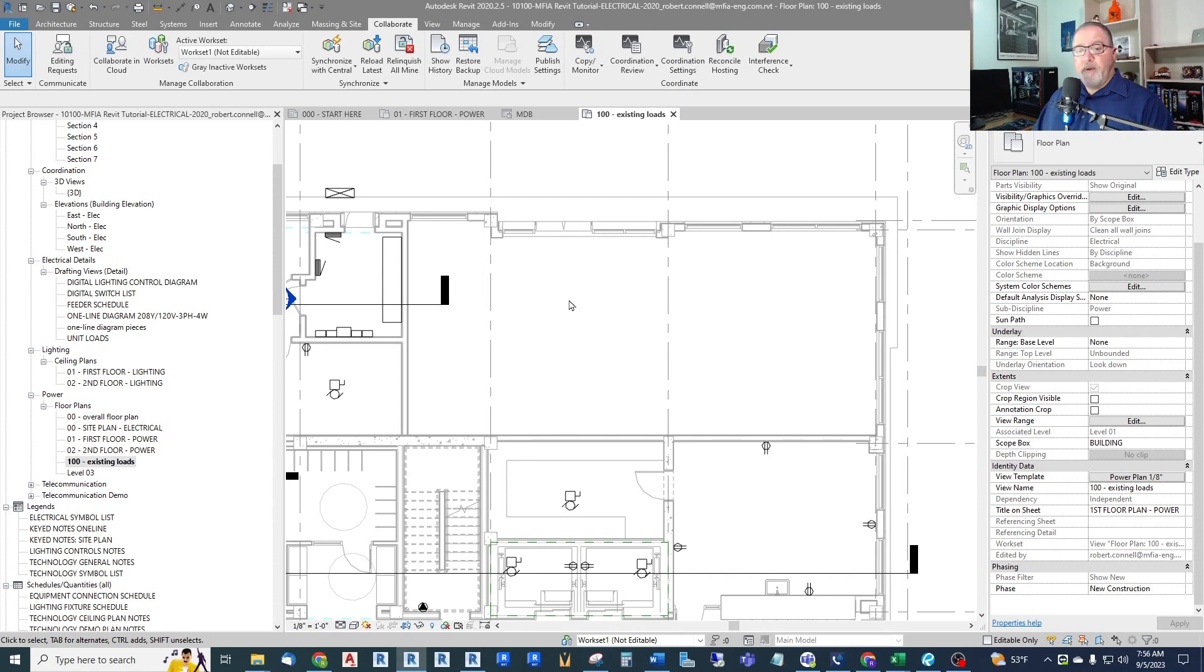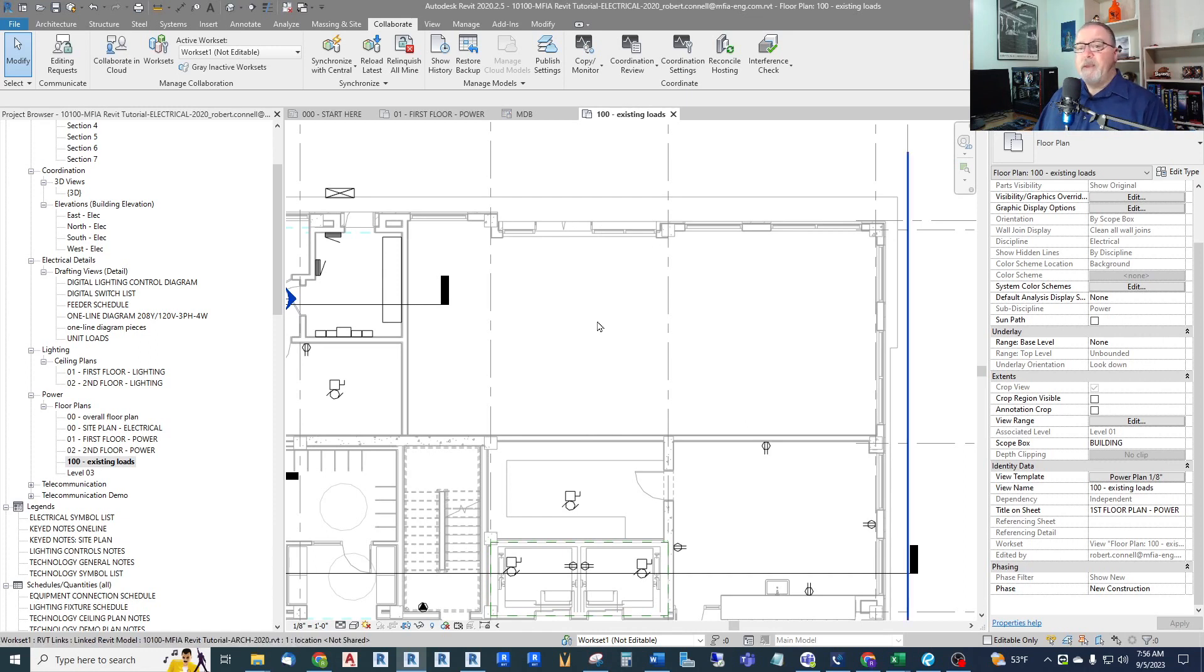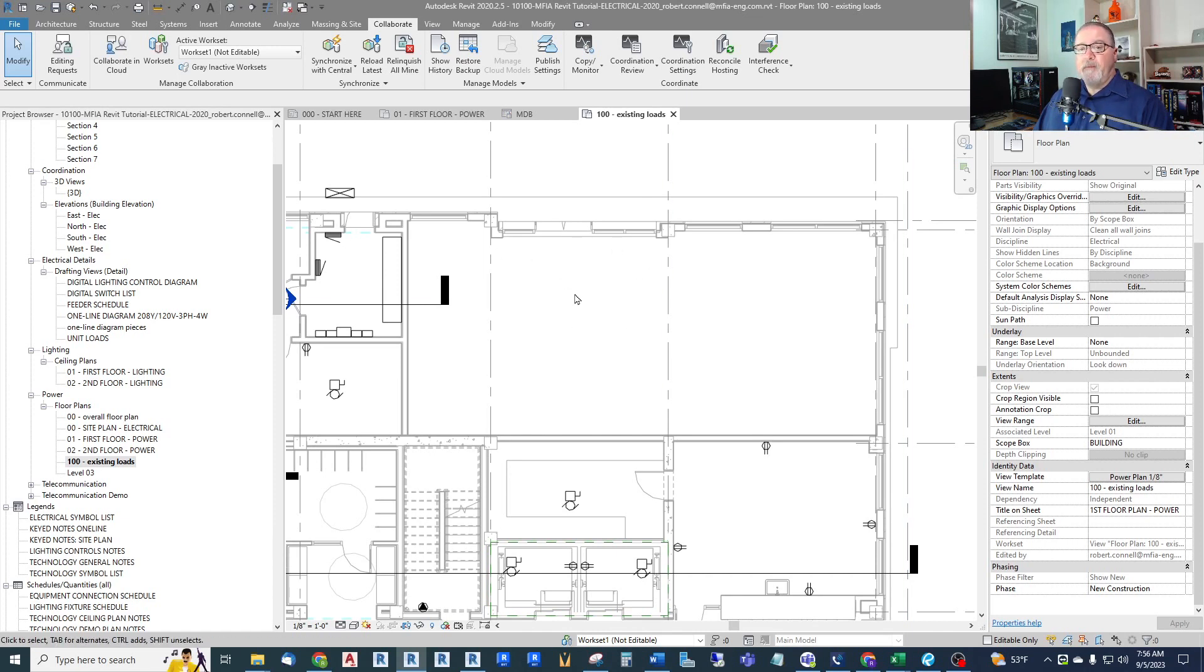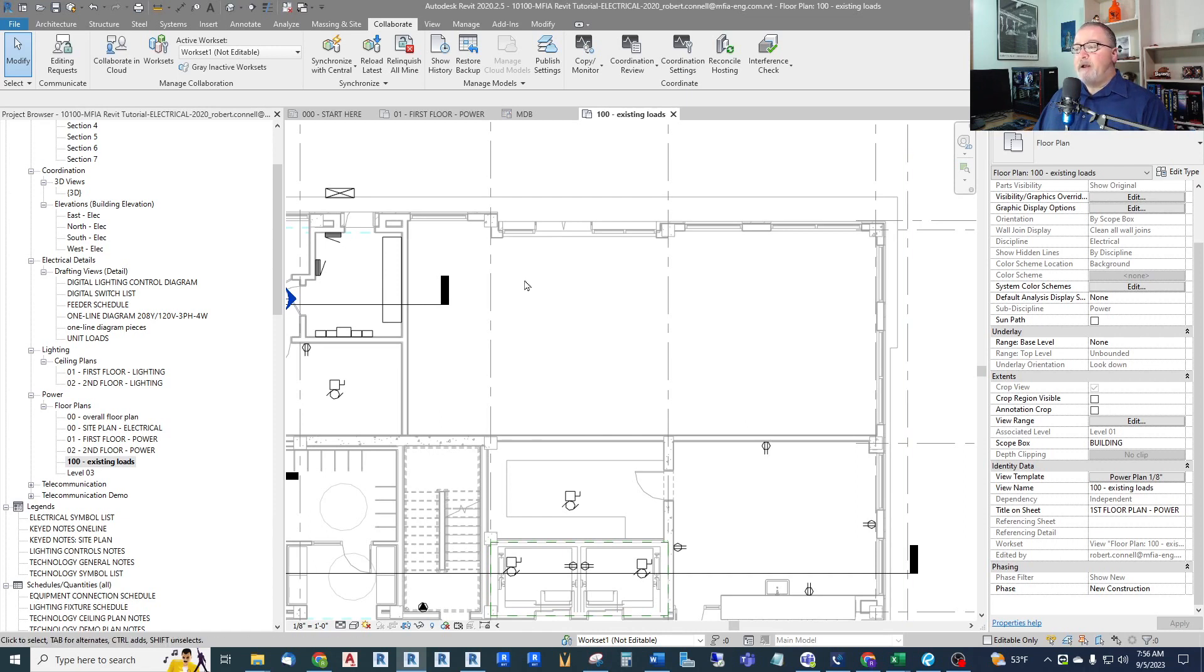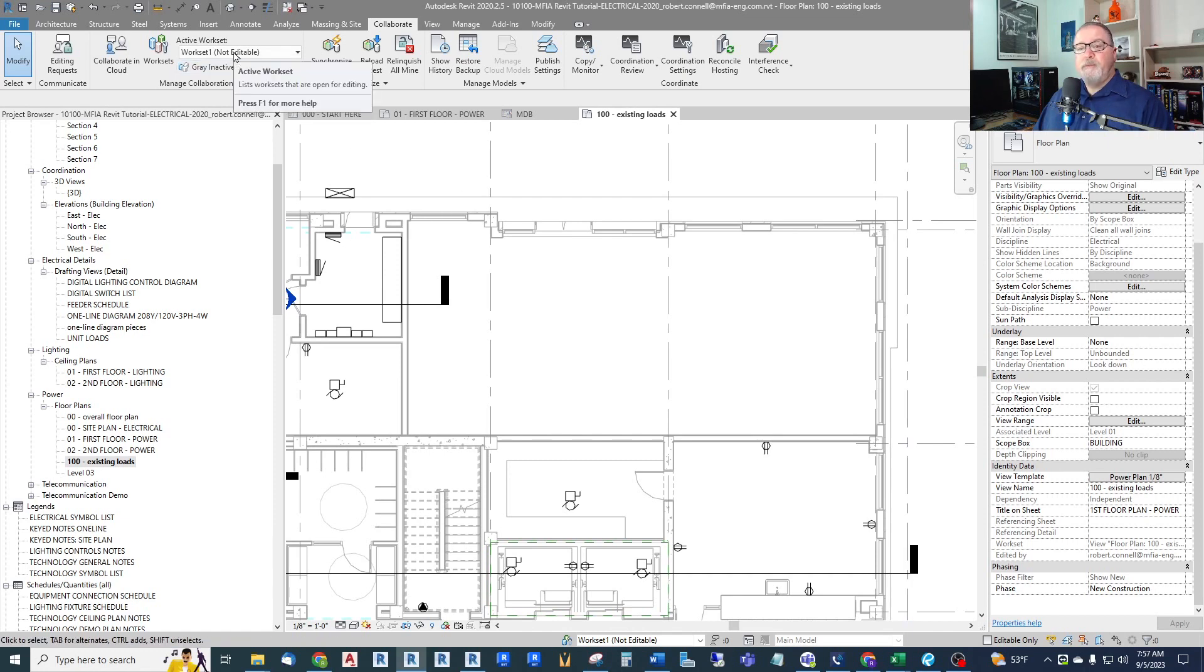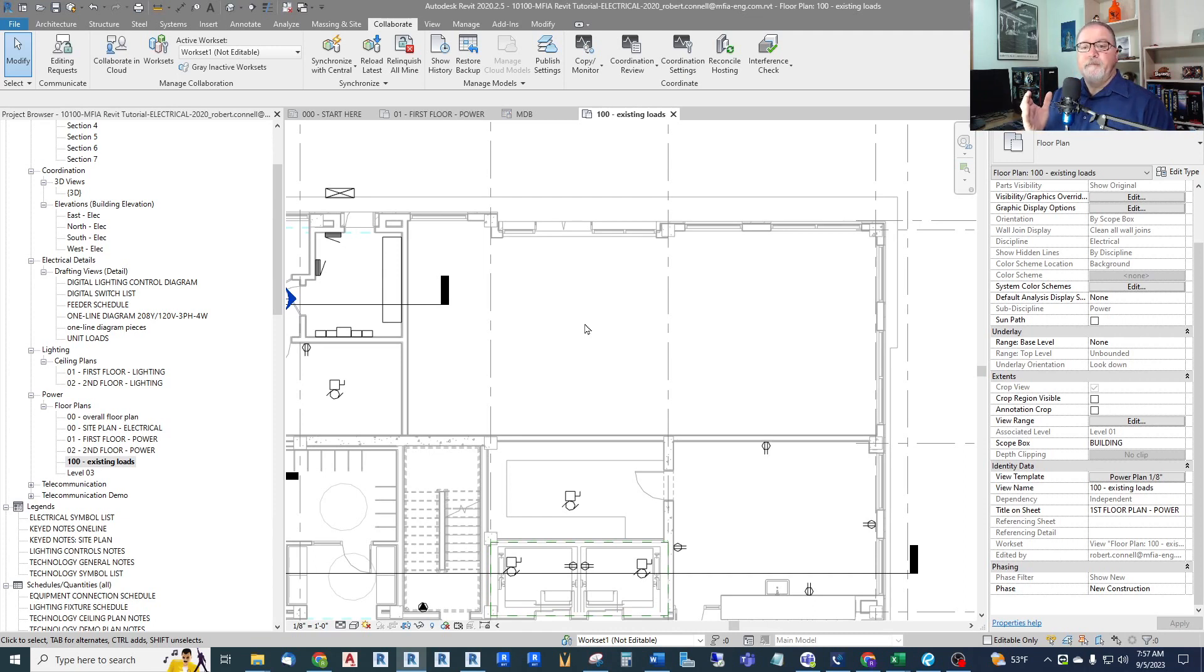I'm not going to publish this. This is purely for adding loads to my load summaries, my panels, my switchboard. So this will just be for showing existing loads only. It's not going to be published. And the way I keep this from showing up on my actual published plans, because I'm not doing the individual receptacle loads here, I'm just using this as a lump sum area, I am going to create a separate work set, put my existing loads on that work set that only shows up in this existing plan. And it won't show up anywhere else, but the loads will show up on my load summaries.